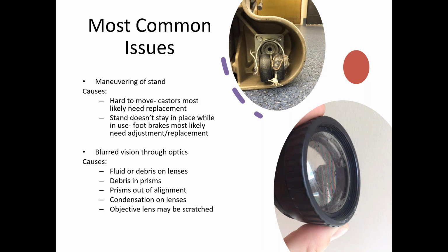If the doctor is complaining about blurred vision, as we mentioned before, the main thing to check is the diopters. Make sure the diopters are set correctly, that they're getting a good, crisp, clear image. Making sure that the bino is seated and tightened correctly. A lot of times this little thumb screw will come loose, and then you've got a bino that's just not seated perfectly, and it can actually cause blurred vision. So these are just little things that you can double check.